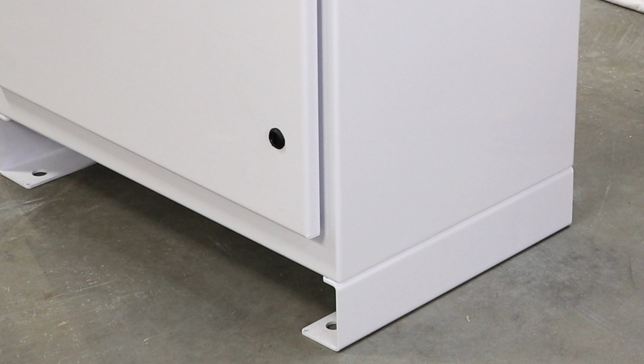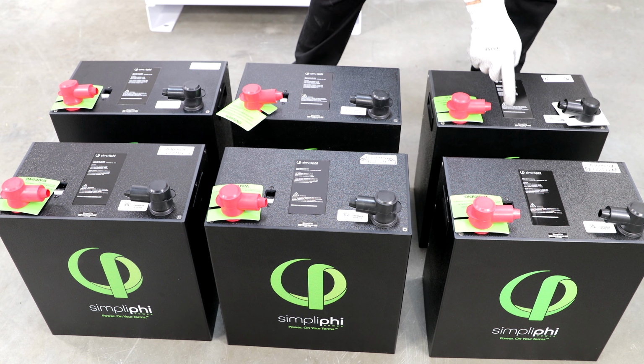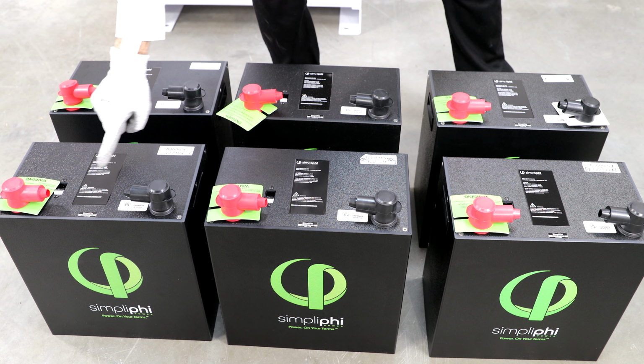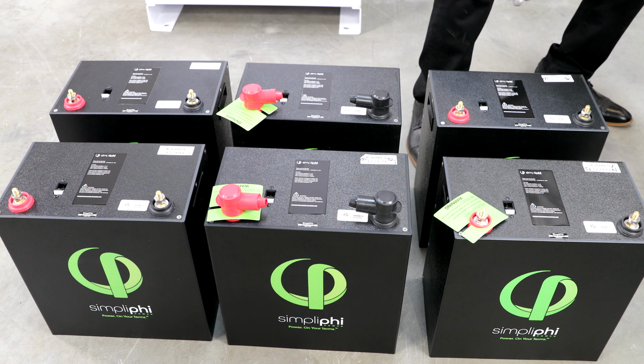Mount the BOSS.6 unit on level concrete. 6 1-inch knockouts are located in the base and mounting feet of the BOSS.6. For a precast concrete pad, a 4-inch minimum thickness is required. Make sure all 6 battery module circuit breakers are in the off position.